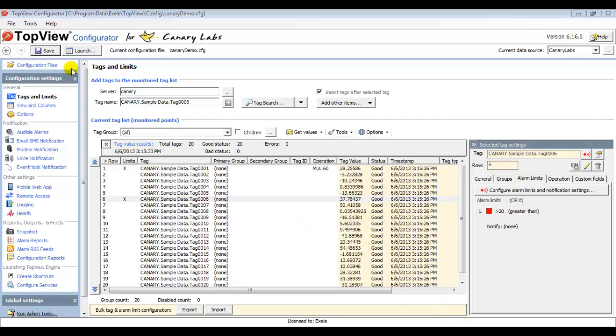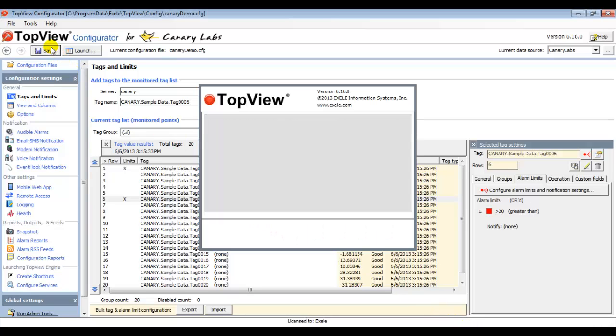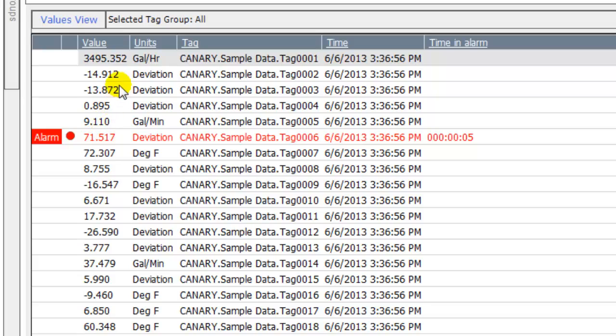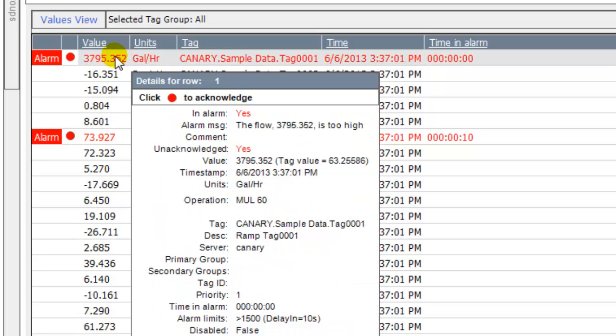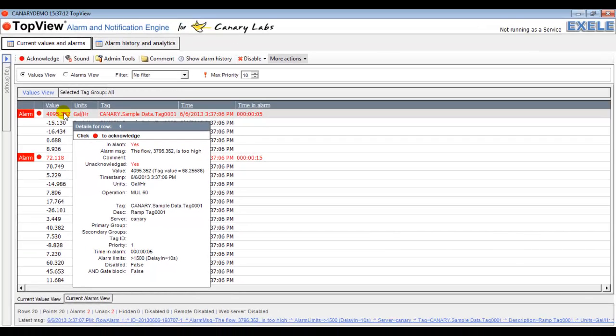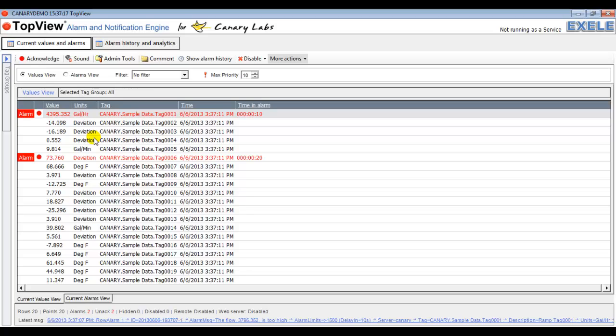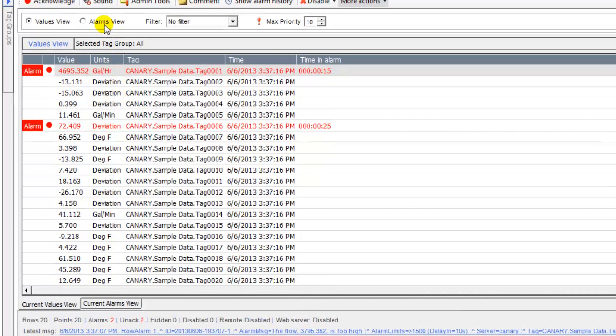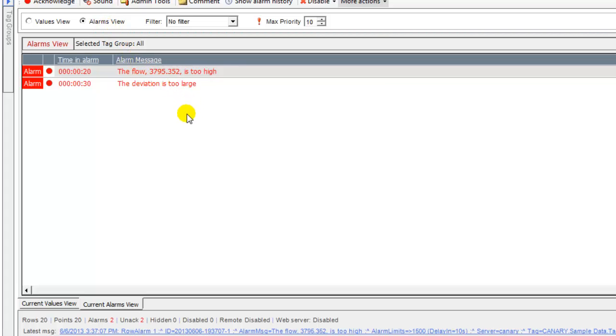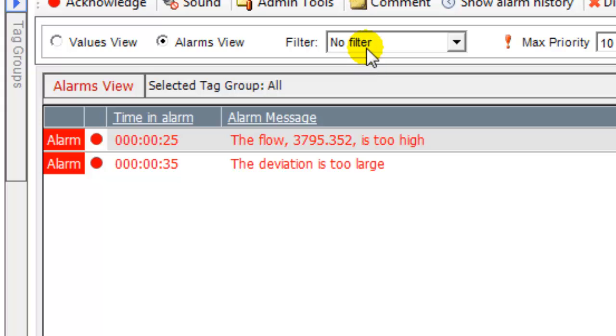To view the result of the most recent changes, I will save the configuration. The Top View engine then reloads the new settings. My sixth tag, the deviation tag, is immediately in alarm because the value is greater than 20. Because the value of the first row is currently greater than 1500, it should transition into alarm after 10 seconds. The Top View engine, the remote viewer client, and the mobile web app present two views of the monitored points and alarms. Values view displays the values of the monitored tags along with the current alarm state of each tag. Alarms view displays the alarm messages of active and unacknowledged alarms. Both views can be filtered and configured to show various details about each monitored tag and alarm.